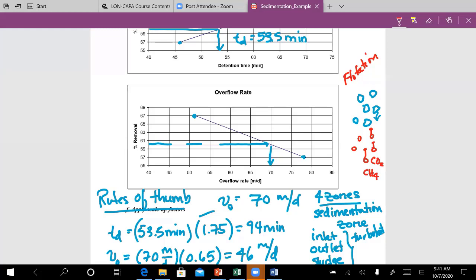On the other hand, at the Lansing water treatment plant, they use gravity thickening because the softening sludge is dense and it's easy to get it to settle. So whether you use flotation or sedimentation really depends on the density of your solid particles.